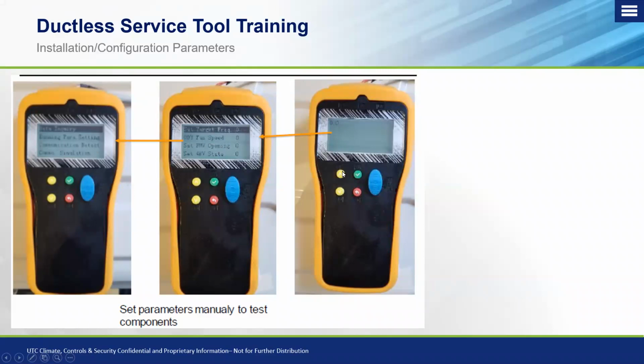If you use your up and down arrows on here and increase this frequency, it will actually send a command. So you turn this up, let's just say we hit this up arrow till it's at 30. We want to run it at 30 hertz. Once we go to the 30, we hit the green OK arrow to send the command, and you'll hear the system or the compressor try to start off.